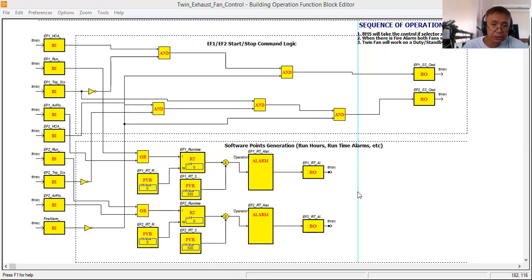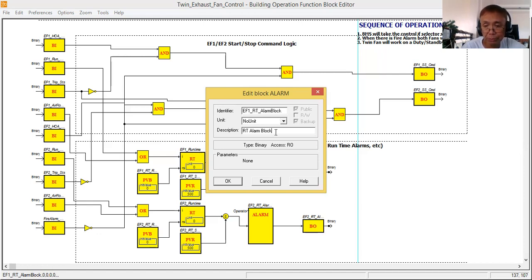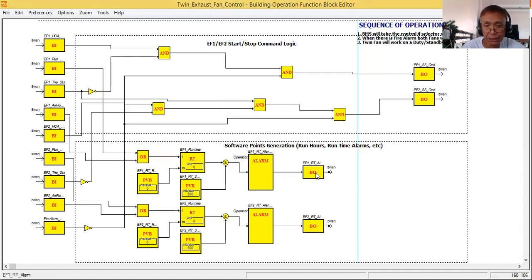Here I introduce an alarm block. You have to properly identify the block — fill in the proper identifier and always put a description. The purpose of the description is for the next engineer who will maintain the program; this is good programming practice. I also have a binary output block here, but this time it will not be bound to a physical point — this is a software point.